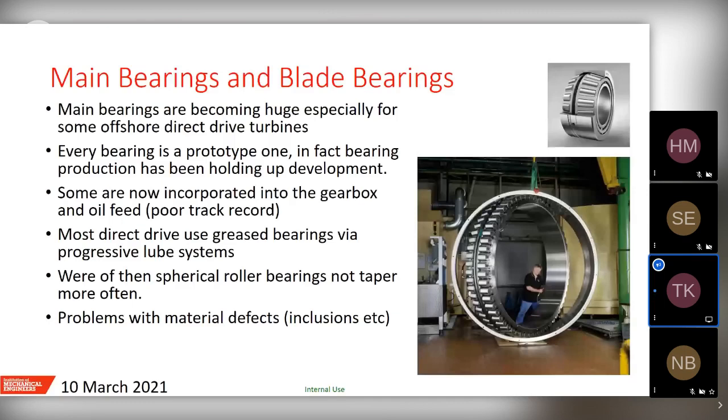Some of the biggest issues we've had up to now are actually issues with materials, because the problem is making turbines this big and bearings this big, you'll find very few manufacturers could make these. And every single time a manufacturer goes out and buys a new, bigger machining system or lathe to make these in a big production. But we're not talking about one-off bearings. You're talking about trying to produce hundreds of these things a year. If they try to do this, they struggle, because it's a prototype every time, trying to find decent quality material of that size, trying to find machines that can do it of that size.